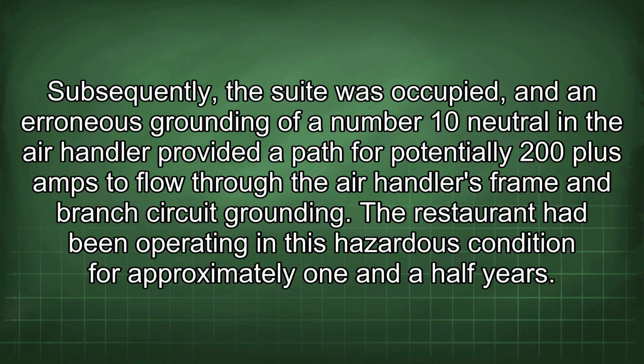Subsequently, the suite was occupied, and an erroneous grounding of a number 10 neutral in the air handler provided a path for potentially 200 plus amps to flow through the air handler's frame and branch circuit grounding. The restaurant had been operating in this hazardous condition for approximately 1.5 years.